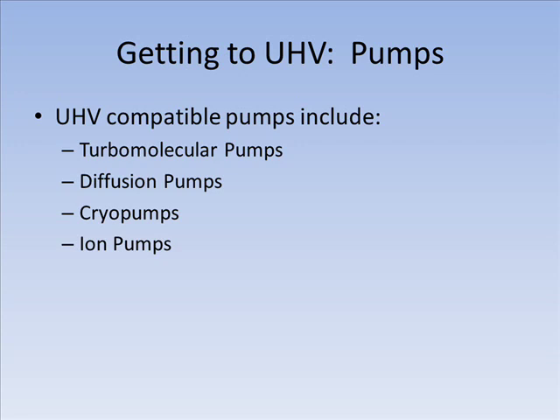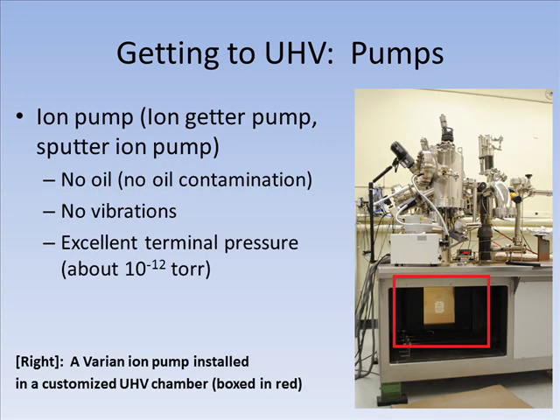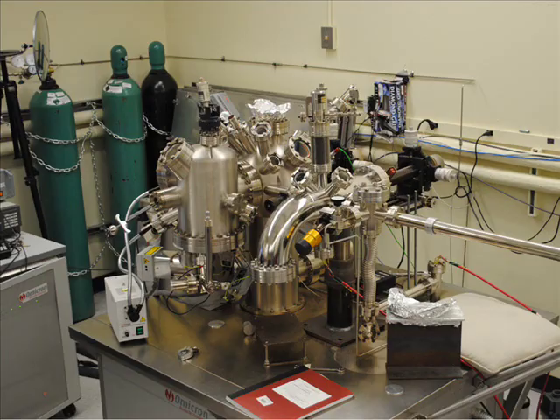A number of pumps can be used to get to the UHV regime, including turbomolecular pumps, diffusion pumps, cryopumps, and ion pumps. Each of these has different principles of operation and advantages and disadvantages. Many researchers consider the ion pump to be the real workhorse of a UHV system, because it introduces no oil contamination and has no moving parts, yet they're capable of attaining terminal pressures lower than 10 to the minus 11 torr in ideal conditions. Many different tools vacuum scientists become familiar with, and most systems are specialized to particular needs, but these videos will focus on showing general techniques useful to anyone new to working with vacuum systems.